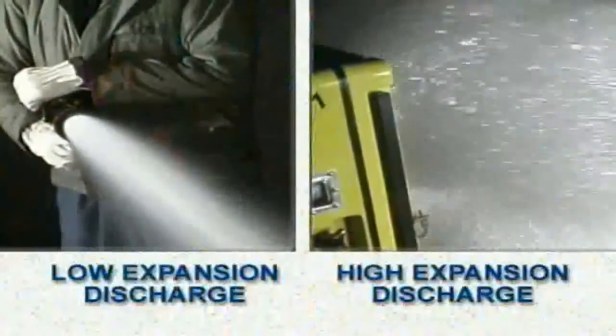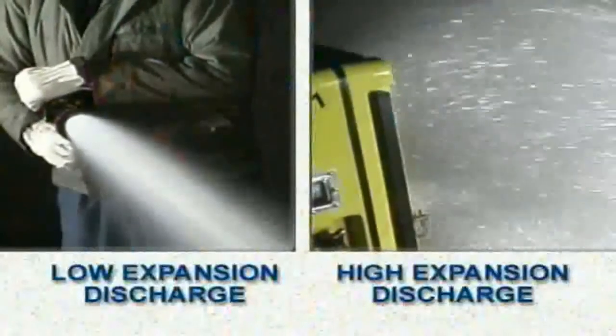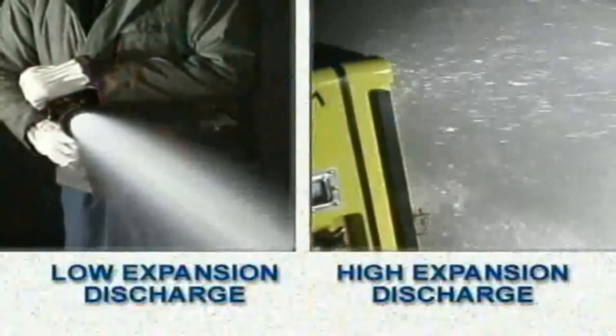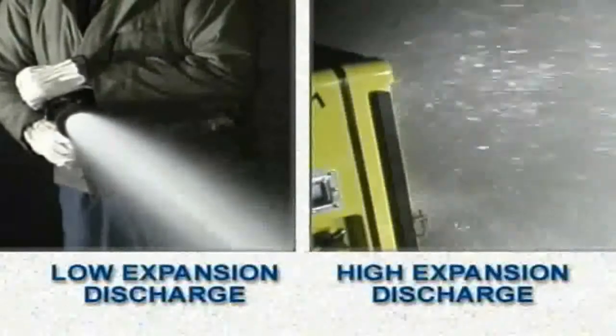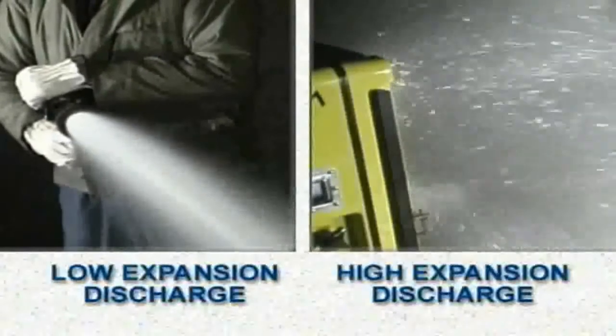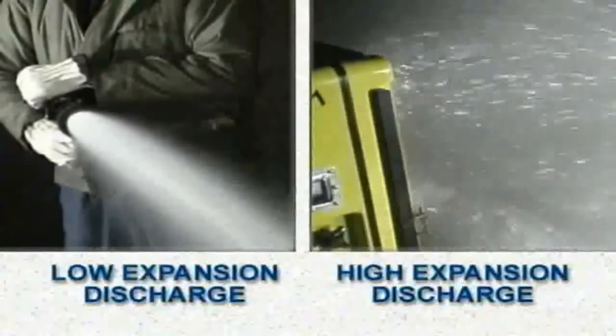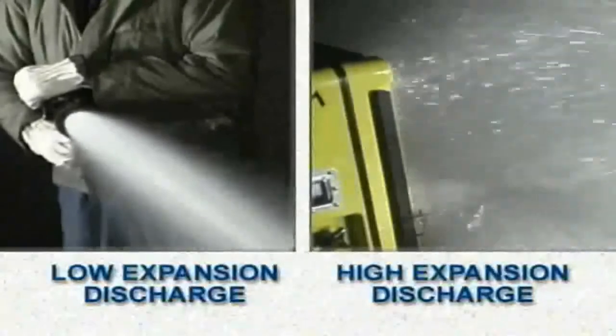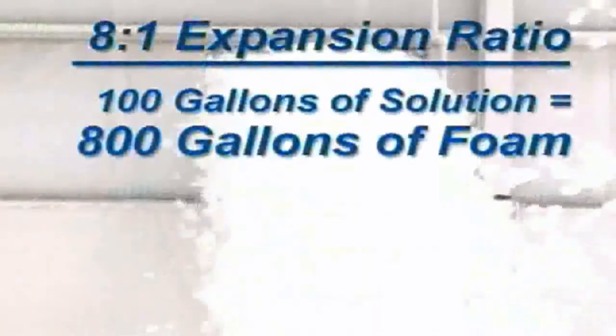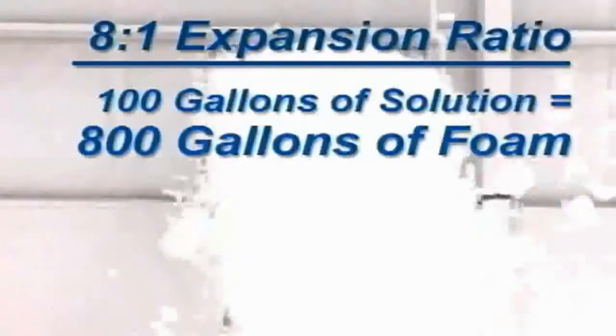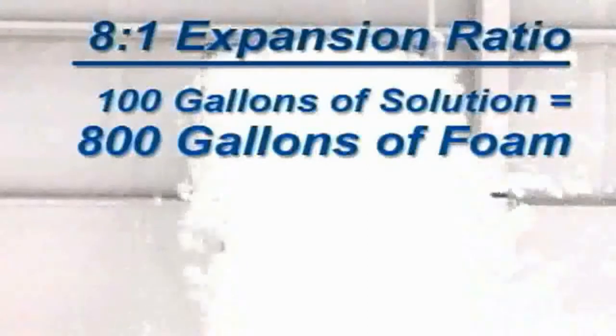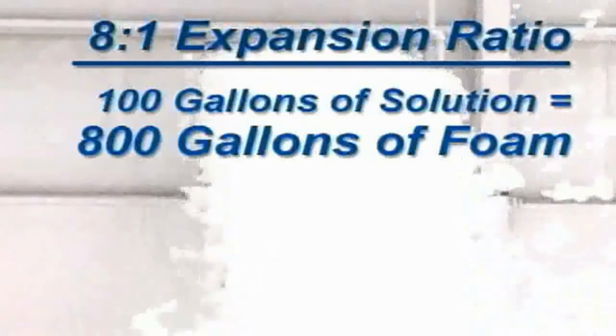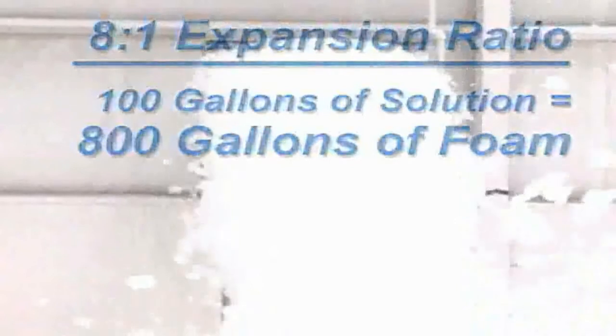Essentially, the difference between high and low expansion foam is defined by expansion ratio, which simply indicates the amount of foam solution needed to generate a volume of finished foam. For example, an 8 to 1 expansion ratio means that 100 gallons of foam water solution can produce up to 800 gallons of finished foam.